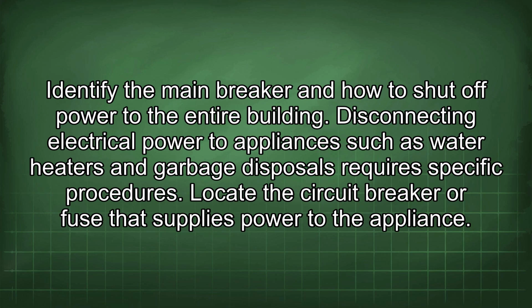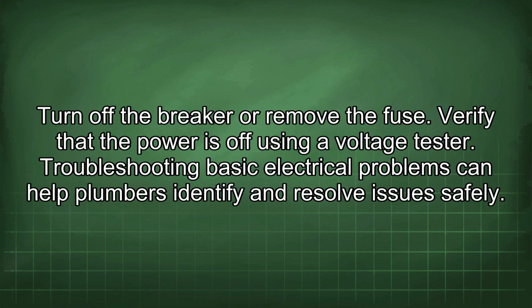Disconnecting electrical power to appliances such as water heaters and garbage disposals requires specific procedures. Locate the circuit breaker or fuse that supplies power to the appliance. Turn off the breaker or remove the fuse. Verify that the power is off using a voltage tester.